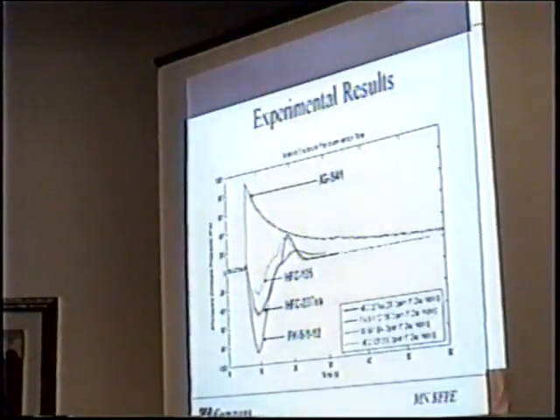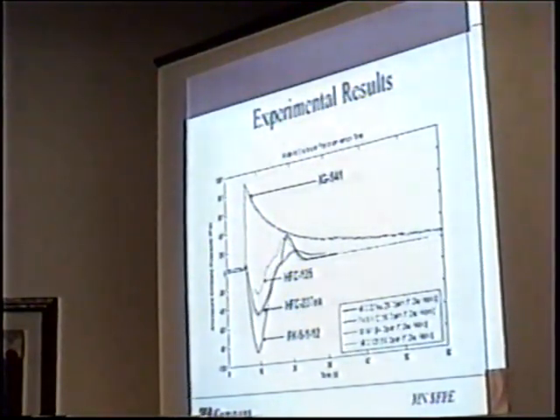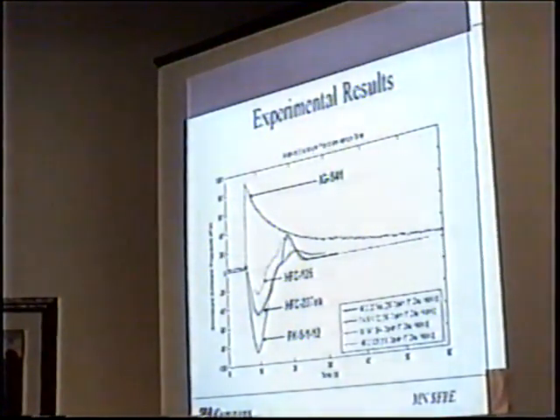Why do we see a negative pressure spike? Well, for the most part, it's because these are very cold agents. They're cooling the air, especially for FK-5-1-12. It's a liquid, and it's evaporating. We're forcing it to by essentially pulverizing it through a nozzle at high pressure. When it evaporates, once again, it sucks a lot of heat out of the air, cools down the enclosure, shrinks the enclosure. We get a negative pressurization spike.